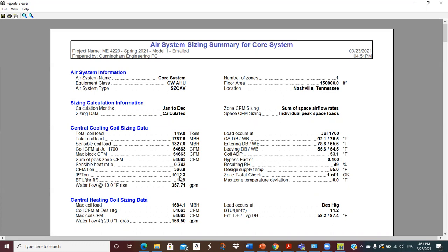Right here on the first page, you see that the total coil load for equipment sizing is 149 tons, which is pretty big — probably wouldn't be one piece of equipment. We see the total coil load is almost 1.8 million — these are thousands of BTUs per hour, so you move the decimal 3 places — almost 1.8 million total, at about 1.327 million sensible, with the difference being the latent.